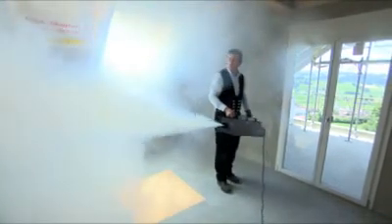To do so, he fills the entire structure with theatrical smoke. A positive pressure is established. It is now possible to see from the outside where smoke is escaping through the building envelope.